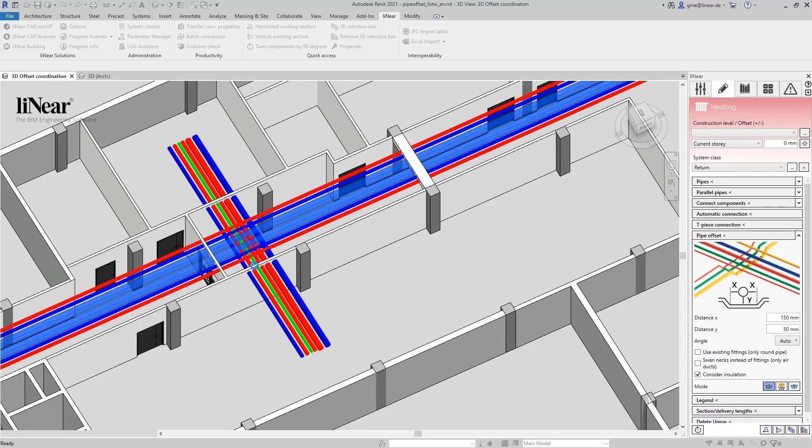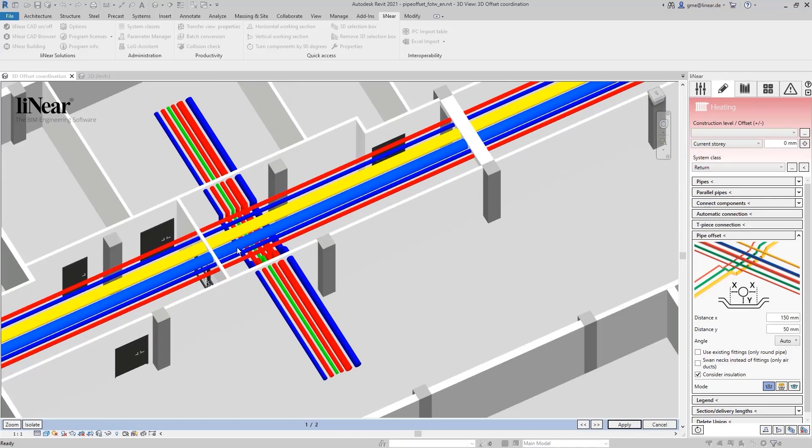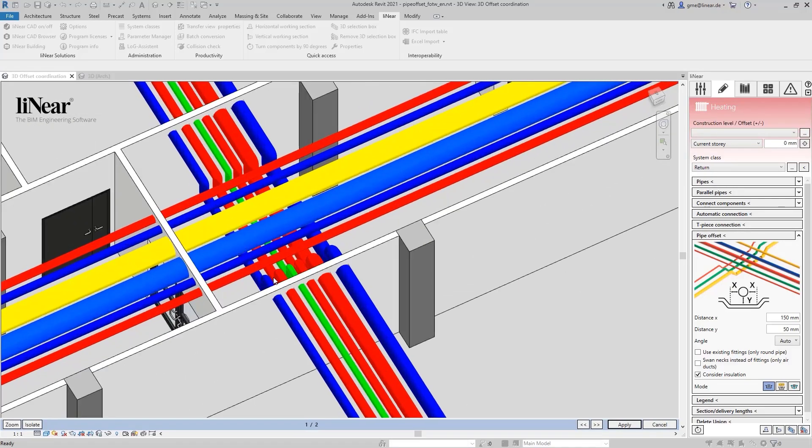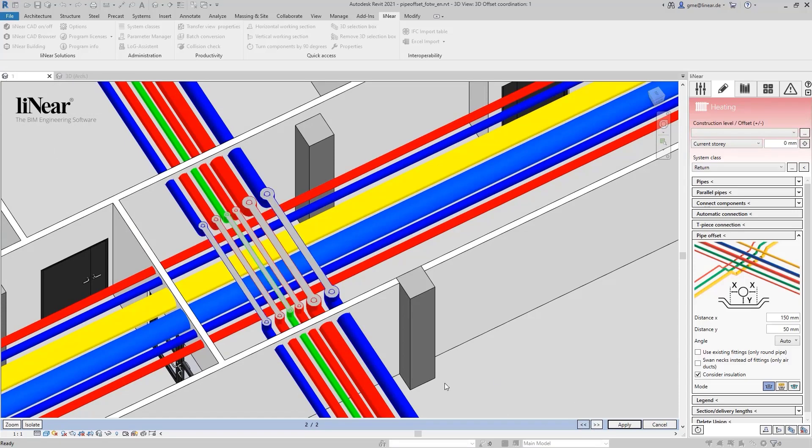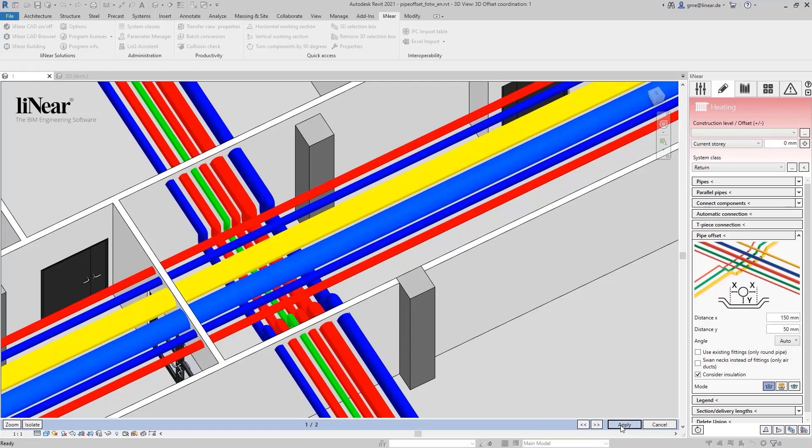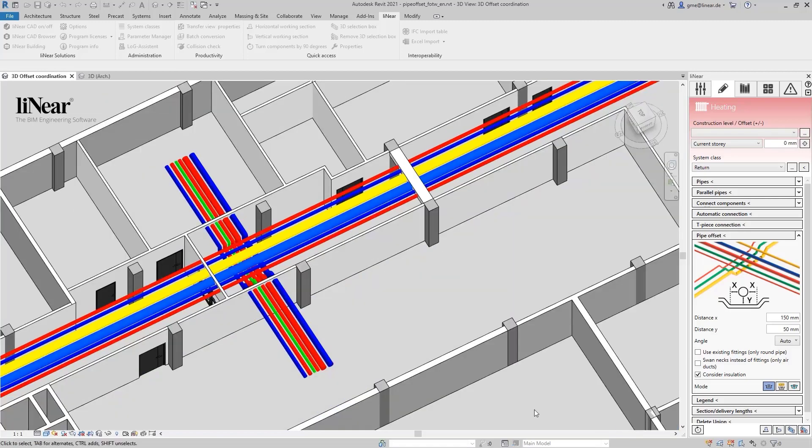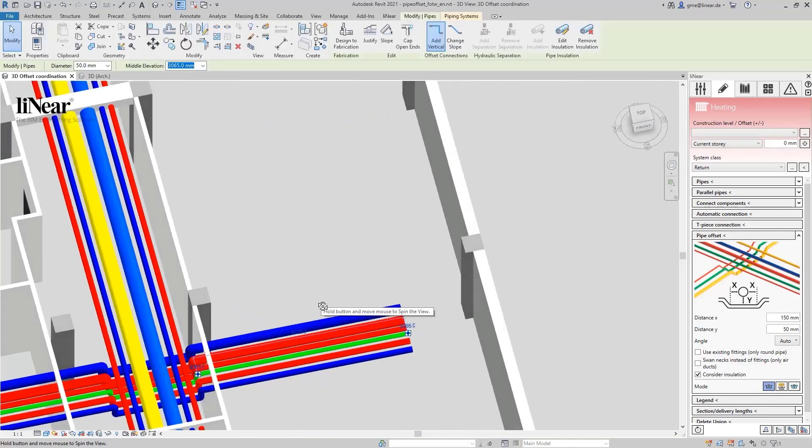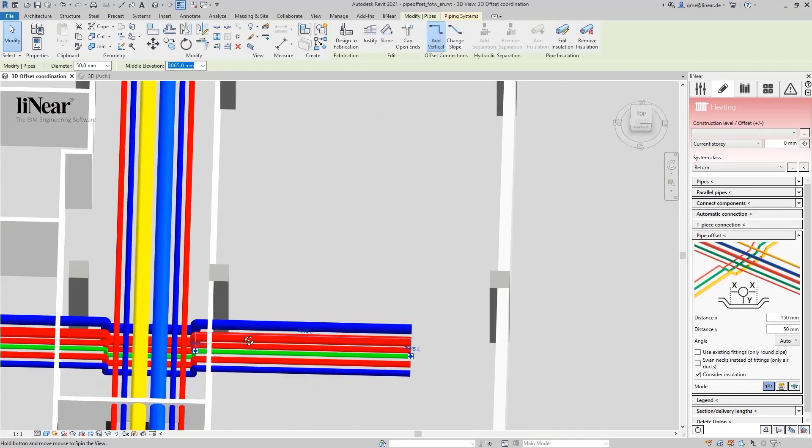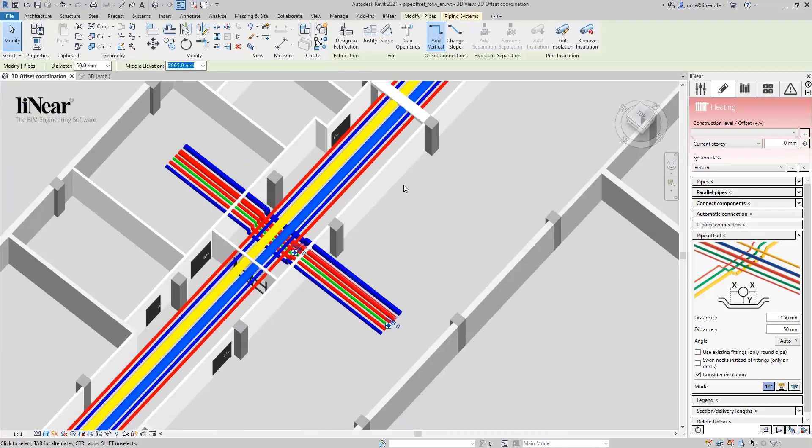The program determines the possible offset variants and offers them for selection. In our case, there are two possibilities. In the second one, we can already see from the selected section box that pipes would protrude into the ceiling. We therefore decide on the first possibility and select apply. Now, the offset is automatically implemented with all chosen elements and the collision is eliminated.